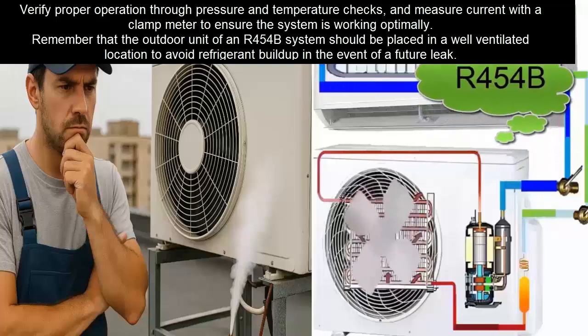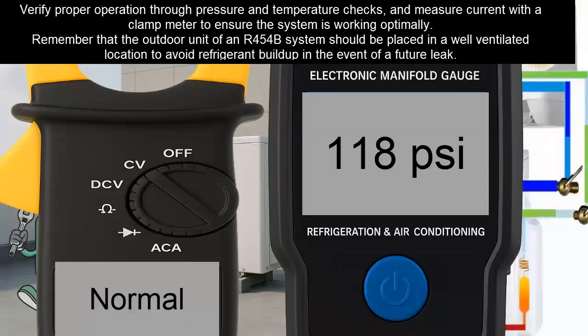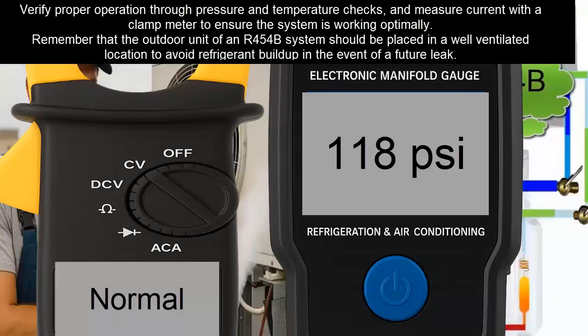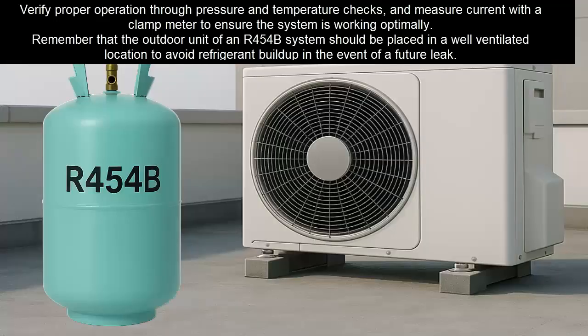Verify proper operation through pressure and temperature checks, and measure current with a clamp meter to ensure the system is working optimally. Remember that the outdoor unit of an R454B system should be placed in a well-ventilated location to avoid refrigerant buildup in the event of a future leak.